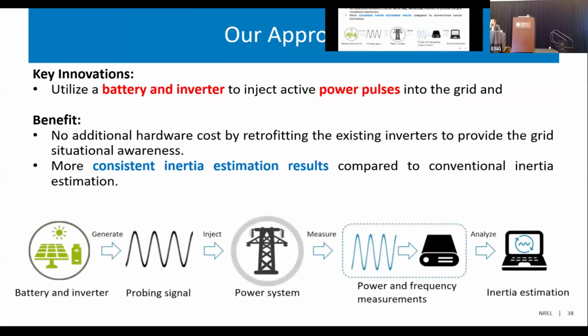Here is how we do it. First, we utilize batteries in an existing hybrid PV power plant, and we use it to inject a small power pulse into the grid. We measure the frequency and power response across the grid at the point of interconnection of the hybrid PV power plant and the synchronous generators, and calculate the system inertia and the inertia from the different devices.